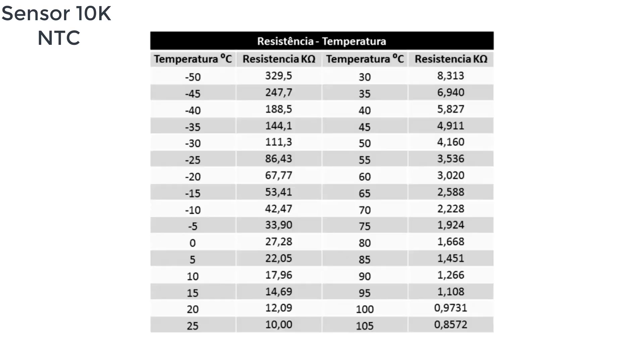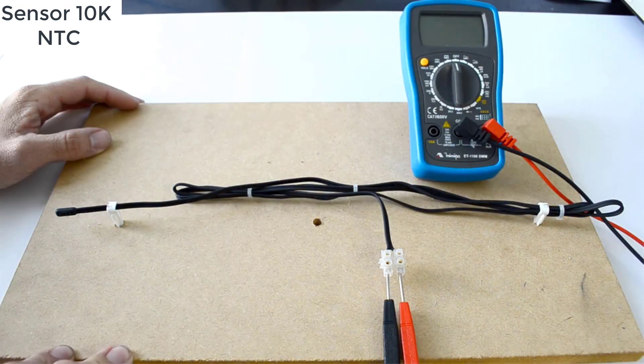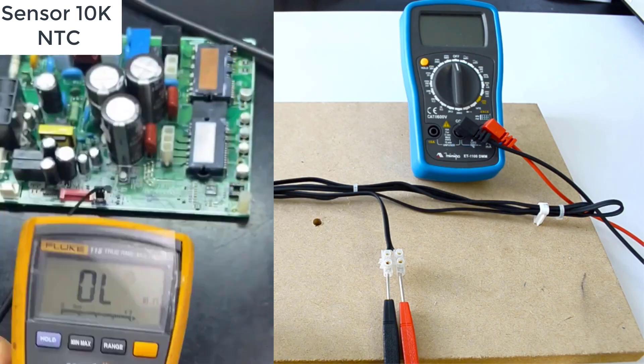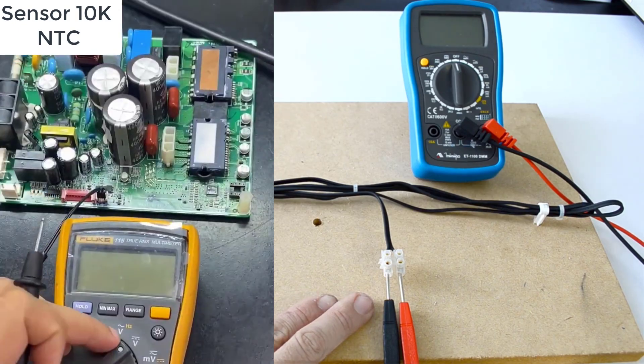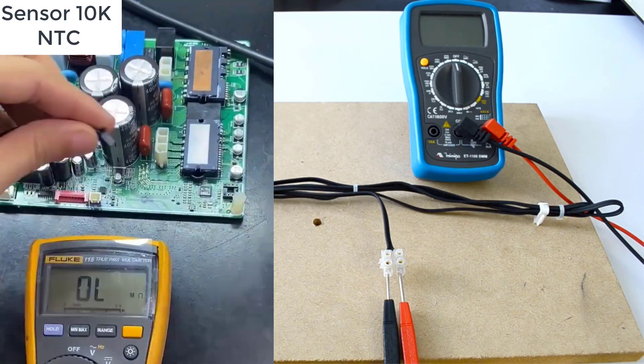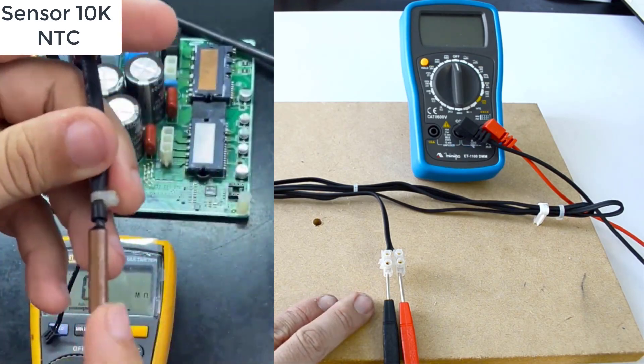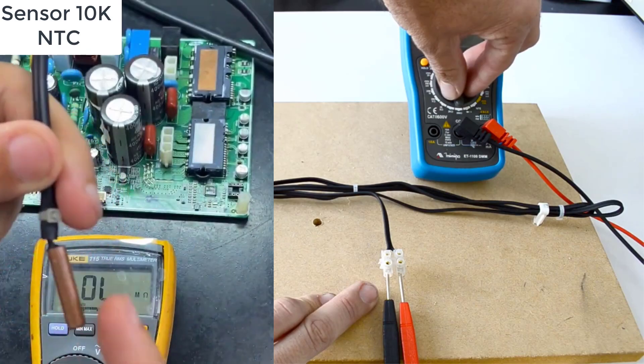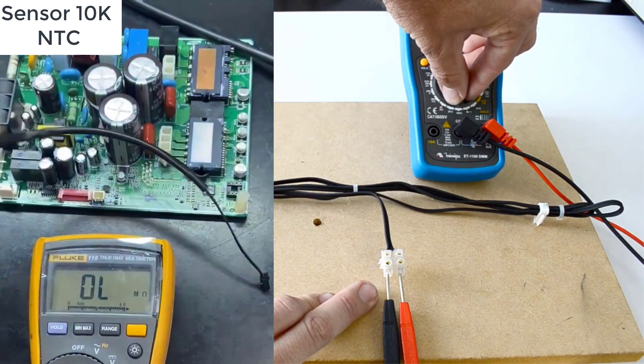We have a table that relates resistance and temperature. You can find this table both in the equipment manual and with the component manufacturer, which provides this technical information as a reference. I placed the two test leads on the sensor. Remember that to measure resistance, there's no need to worry about polarity. I set the multimeter to the 20-kilohm scale, but you can choose a scale close to the value you are going to read.